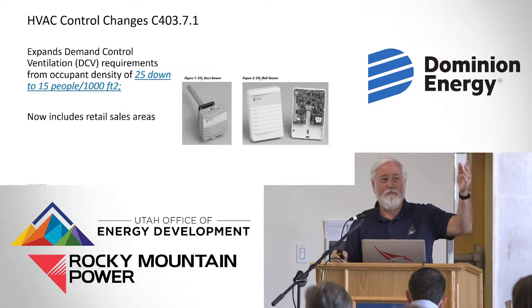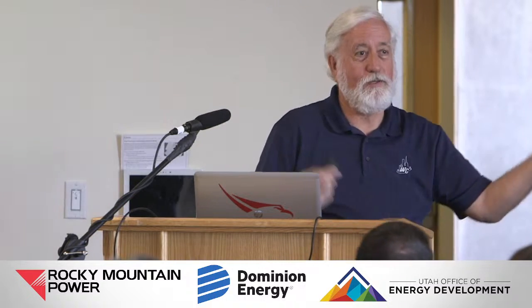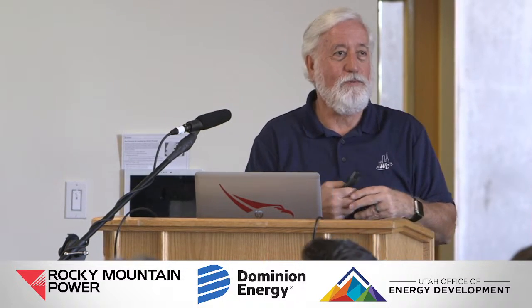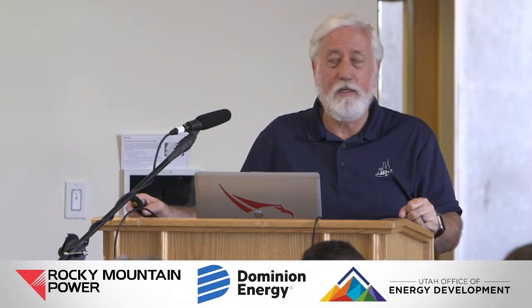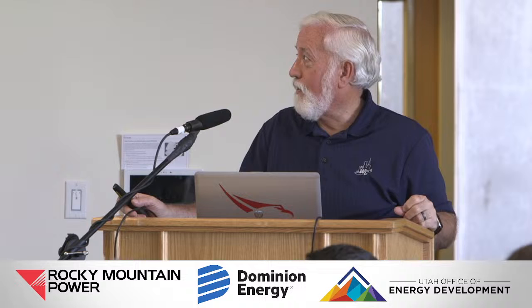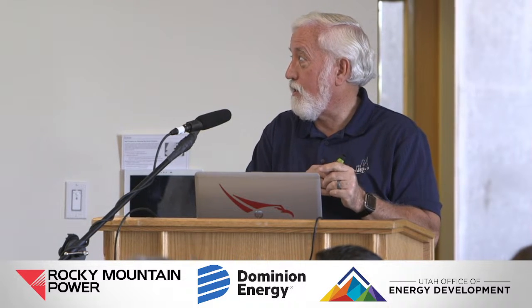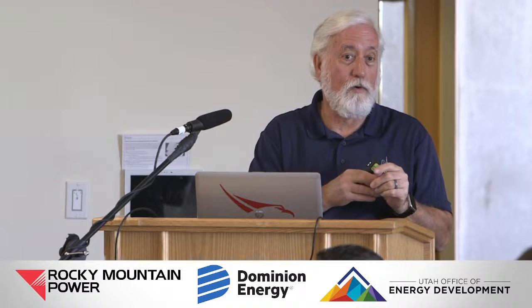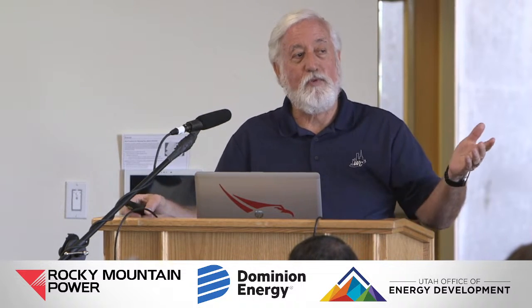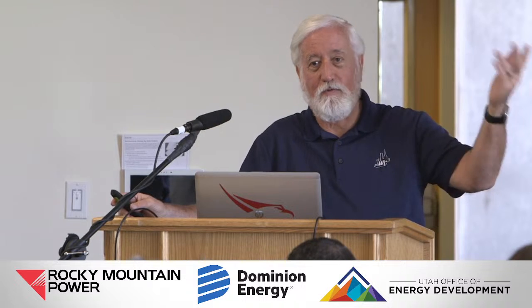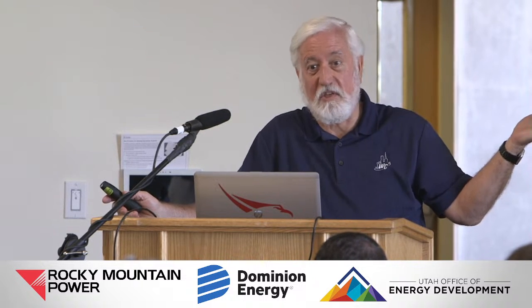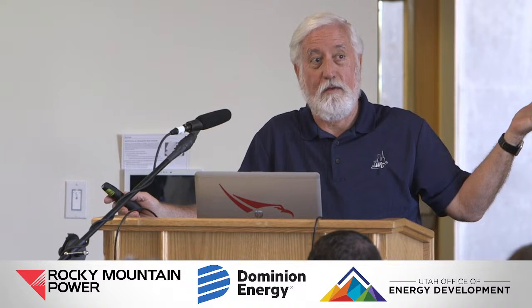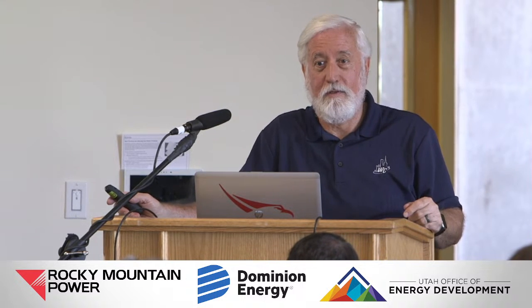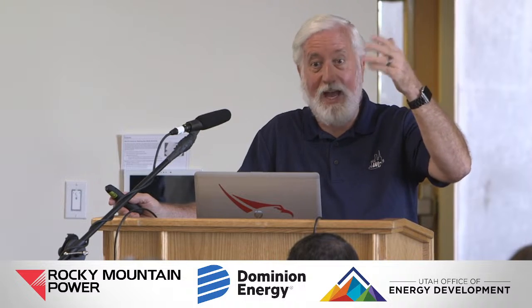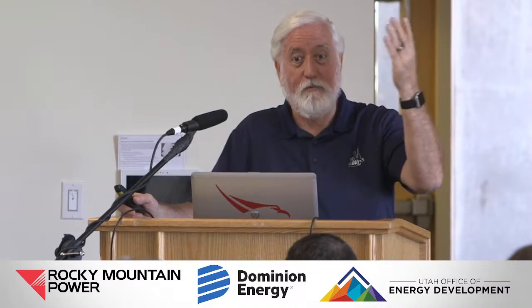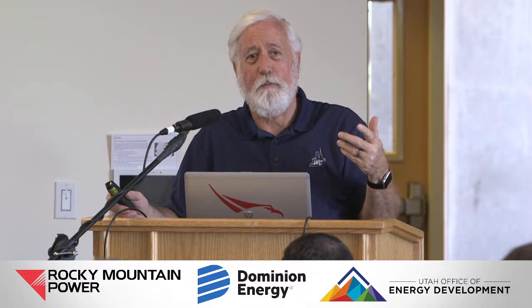How many people could we put in this room? Might even say someplace. 80? 52? It's bigger than 500 square feet. We definitely have an occupancy listing or rating on this building that's higher than 15 people per 1,000 square feet. When the building's empty, how much ventilation air do we need in it? How much fresh air do we need to come in from outside? Really zero, right? Well, no one's in it. What about when we fill it up? We need so much, 7.5 CFM per person, plus a little bit for the square footage. So we need a certain amount of CFM.